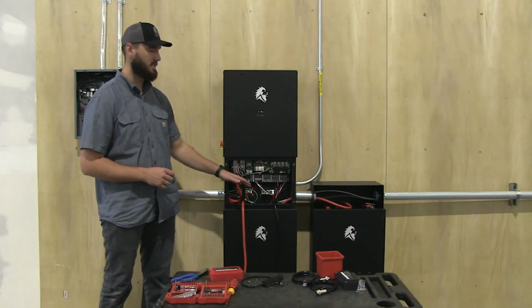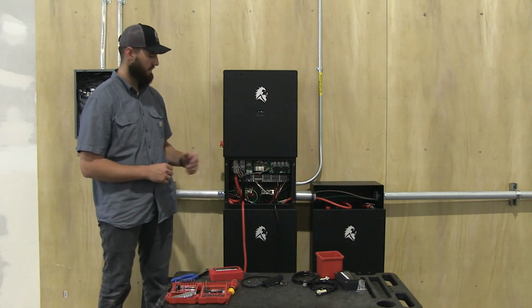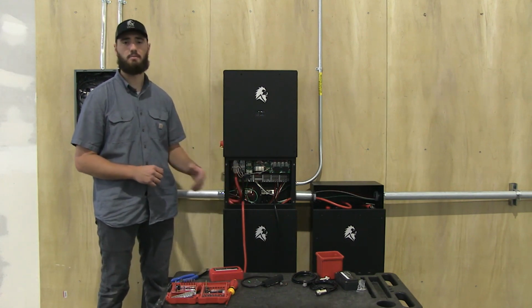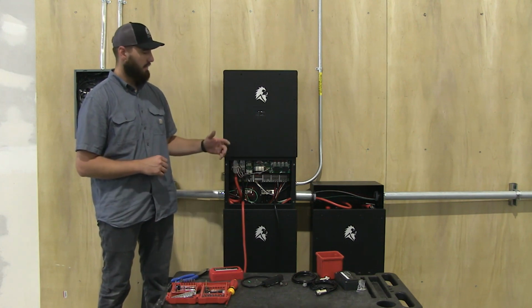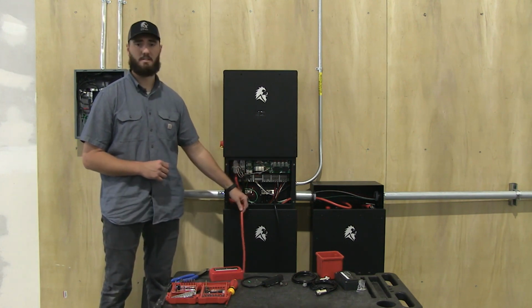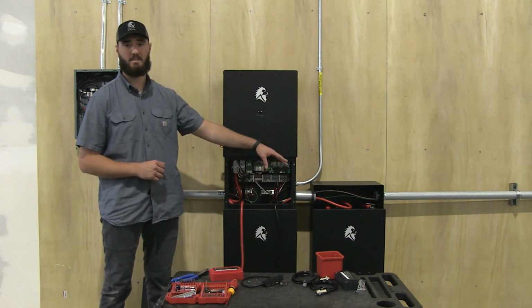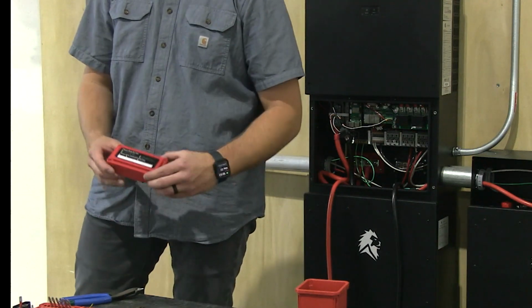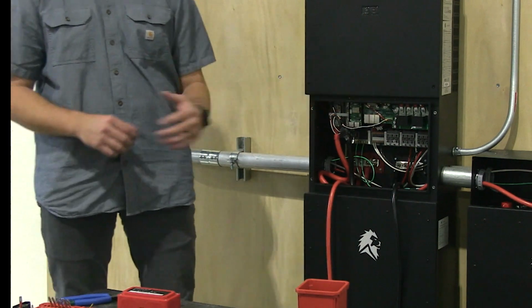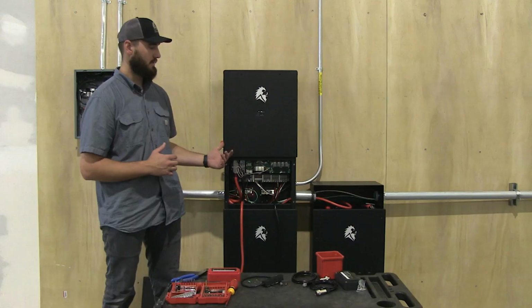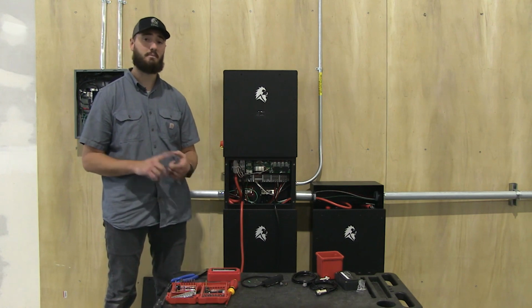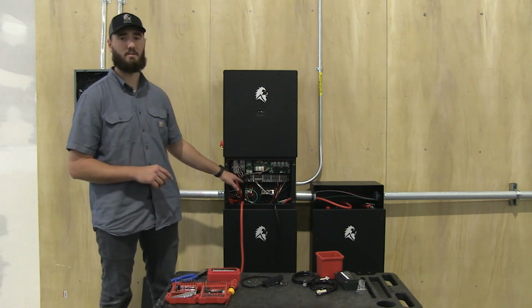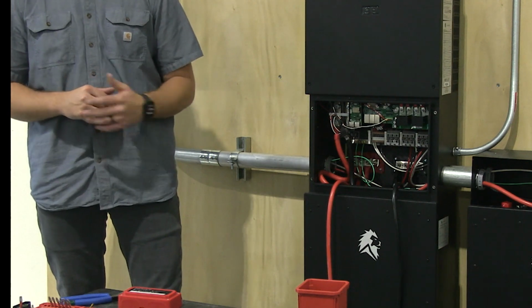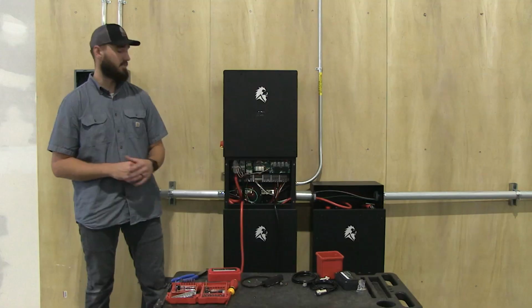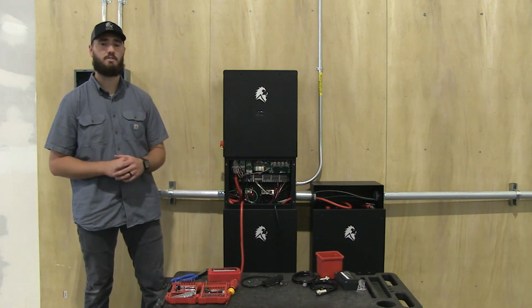At this point, we've installed our bus bars beneath the inverter and connected our eyelet to eyelet cable to the bus bars. We've also connected our battery cables from battery 1 and battery 2. We can now install our bus bar covers and then connect our battery cables to the batteries. This will allow us to have the batteries in parallel and connected to the inverter. It's important to note that after connecting the battery cables to the batteries, the terminal beneath the inverter will be hot, so use extra care from here on out.